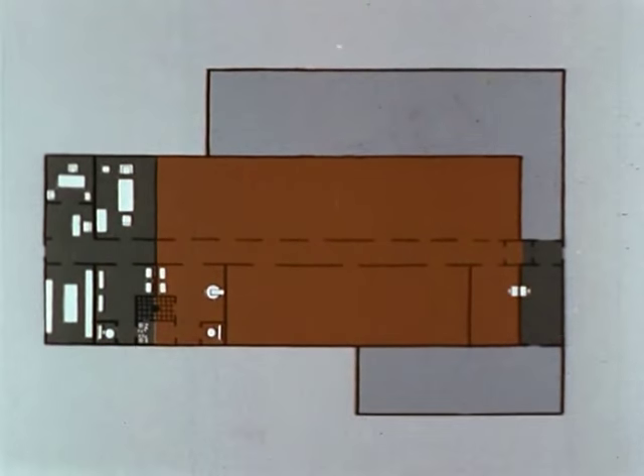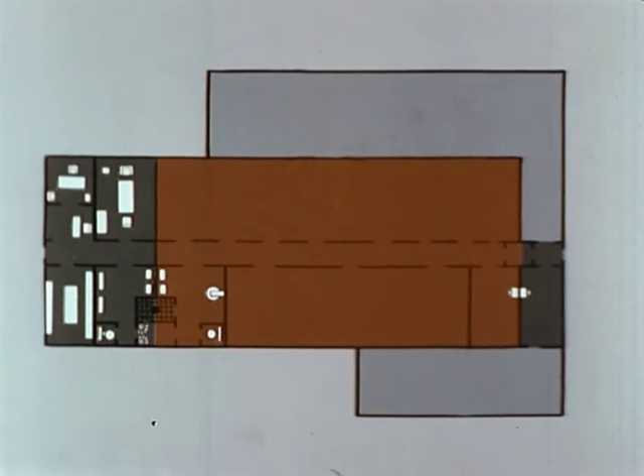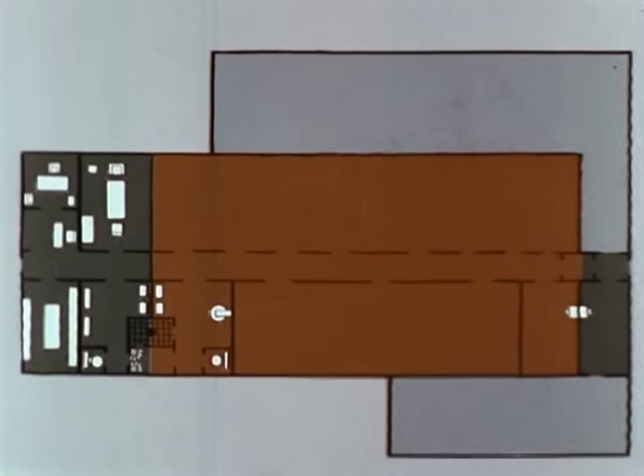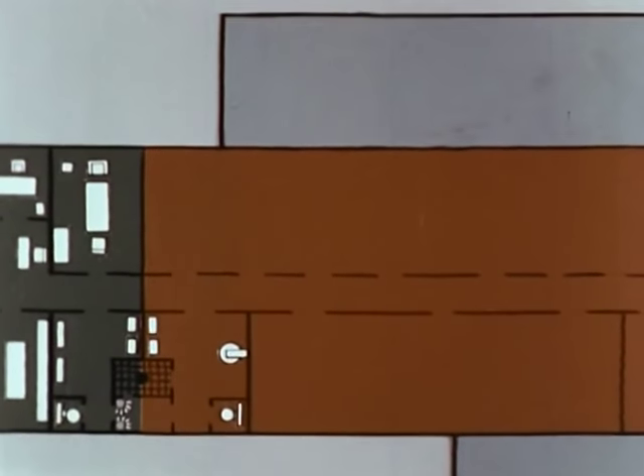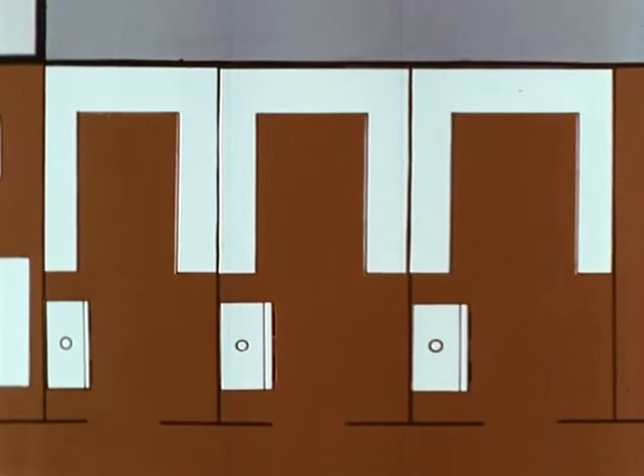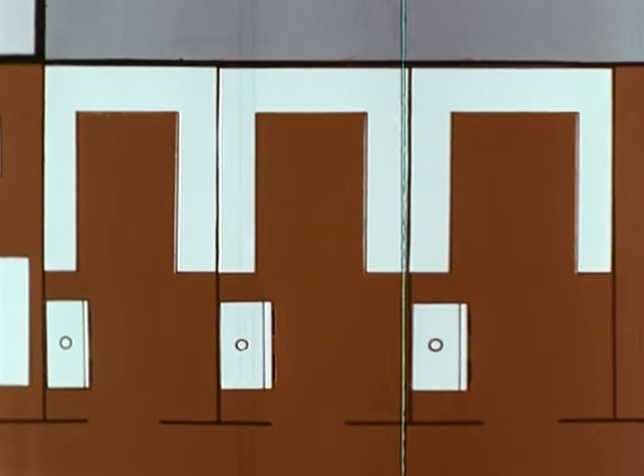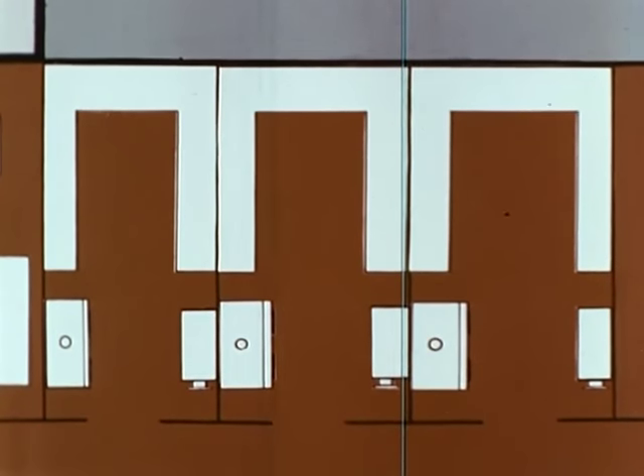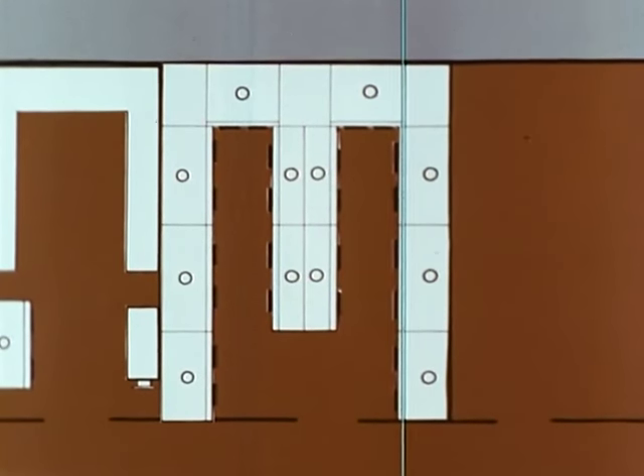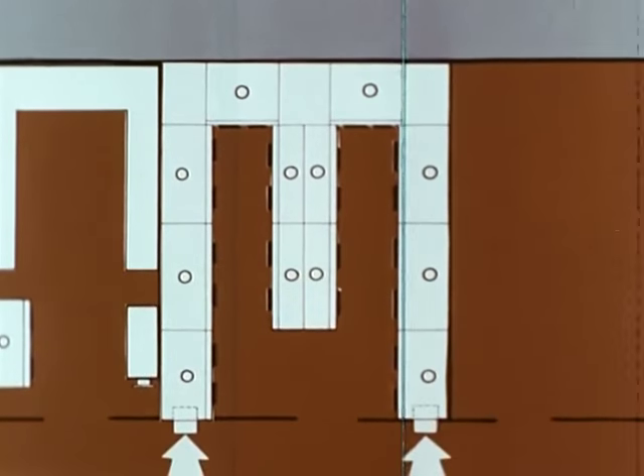Returning to our floor plan, let's look at the second functional zone of a typical facility, the lab research area. Here, infectious microbiological operations exclusive of animal work are performed. Located in this area are the potentially infectious lab offices. The individual laboratory rooms are usually equipped with one partial barrier safety cabinet for work of low to medium risk and a freestanding single door autoclave. At least one room should contain a gas tight absolute barrier cabinet system for performing high-hazard operations with a minimum hazard. The system should terminate in either a double-doored autoclave or a germicidal liquid bath.